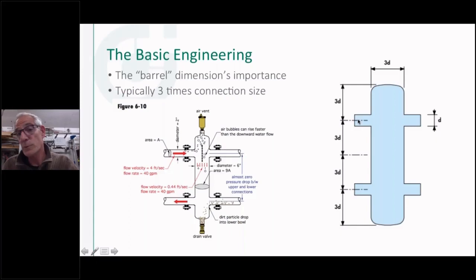If this is a 1 inch, which is one of our more common sizes, then 3 inch would be plenty here, 3 times 1. If this was an 8 inch pipe coming in here, which we make, then you're getting pretty big. You're talking about a 24 inch diameter vessel to give you that 3-to-1 relationship. Now I will say on the bigger sizes that number does go off a little bit. If you buy our 14 inch hydro separator, with 14 inch pipe size coming in, it isn't 3 times it. I don't know if Kevin knows that off the top of his head, but at some point we actually calculate the space in there and come up with it.